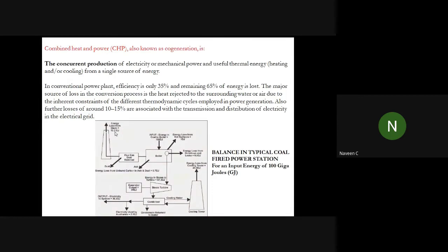Okay, but one of the main things, mechanical engineers, please note this down: you cannot reduce the stack temperature below 110 degrees Celsius. There may be a question which will be asked generally in an interview or any practical: why can't you reduce this energy loss? You cannot reduce this. Why? Because there is a term named sulfur dew point.